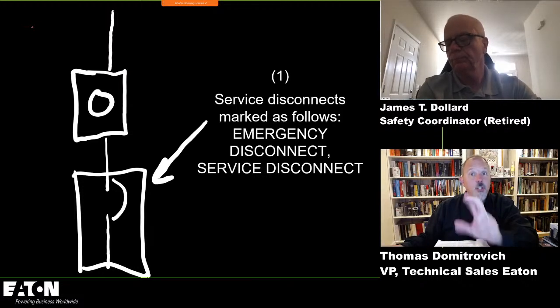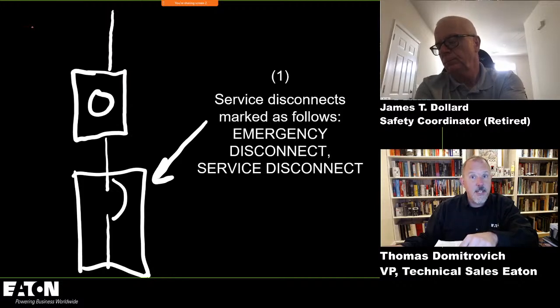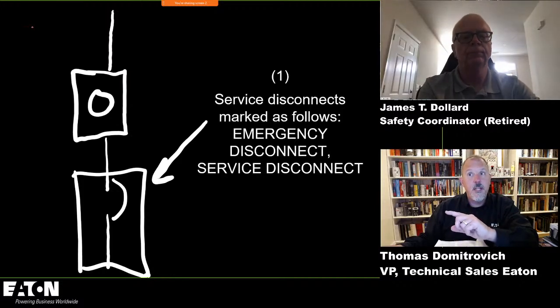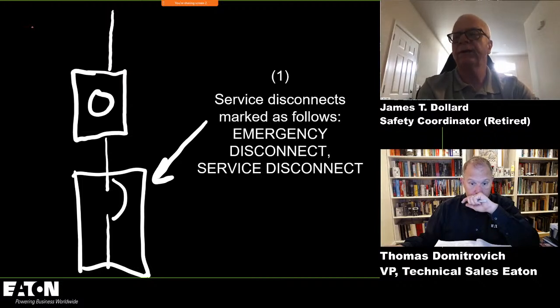So there's also, I think, batteries and generators both have requirements for that. Energy storage systems have a requirement for a disconnect, and then on the PV side of the world, that has the rapid shutdown, which covers all this. So there's nothing that was needed in the PV world. Yeah, and the only significant difference there is, we require a line disconnect here, and we require the capability to shut down the generator. But with an energy storage system, you can actually have a shunt trip.